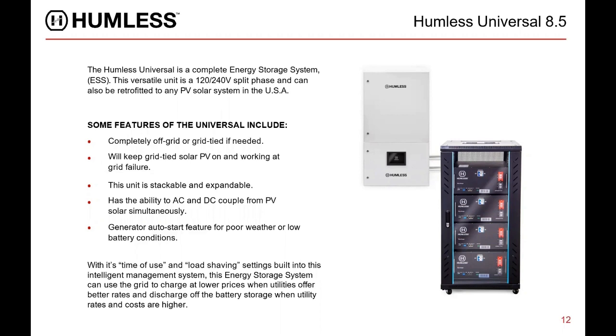Any true microgrid, if we were off grid, for example, here's an example I call the 90-10 rule. 90% of the time, if we properly size a system, even 95% of the time, the system does its job. But you prepare for that 5-10% of the time. I live in snow country here where we build these systems in Utah. And if it snows for 3 days, in off-grid situations, batteries can be getting low. The generator feature is just a nice thing to have. Now, it's not necessary. A lot of grid-tied homes don't need it because maybe their power outages are shorter durations most times. But it's a feature that's available, and it's a feature that they can add a generator at a later time.